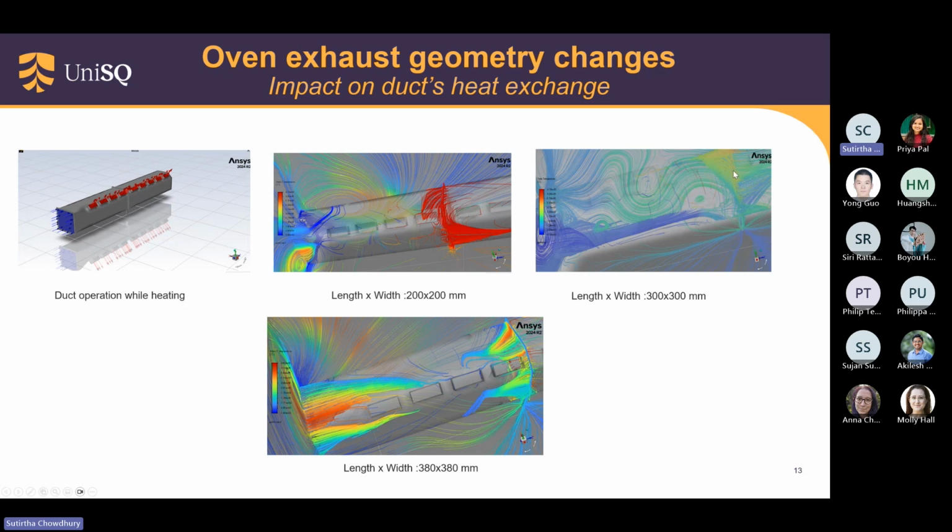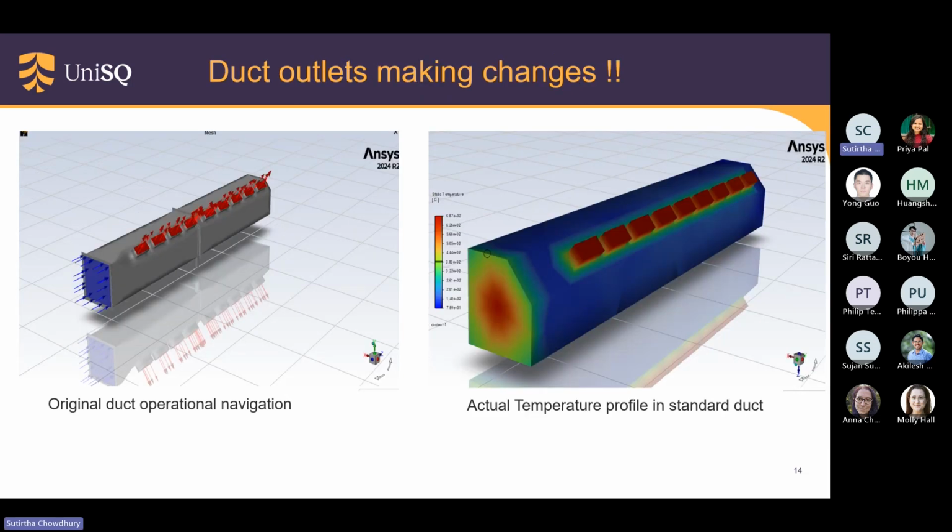270 degrees Celsius inside the dividers throughout the ovens, but it cannot be considered good enough for a good capacity. Afterward, in 380 mm, it gives a more saturated temperature and better temperature profiles, which tells us that it will create 350 degrees Celsius on average.